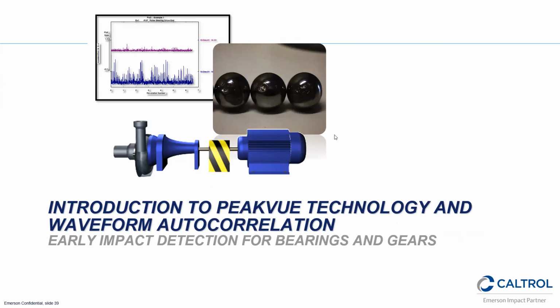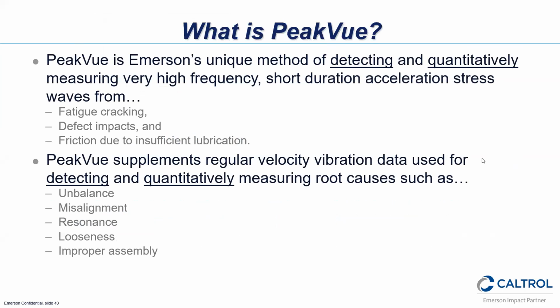Now we'll get into PeakVue. So every manufacturer, you'll see bearing faults in standard data, which most analyzers are collecting, and it happens way high up in the acceleration spectrum, and you usually don't see anything until they've gotten to the point where they're about to create a catastrophic failure. But Emerson has developed a technology called PeakVue, which filters out all the low frequency amplitudes and only looks at metal to metal impacting. And basically what I just said right there.